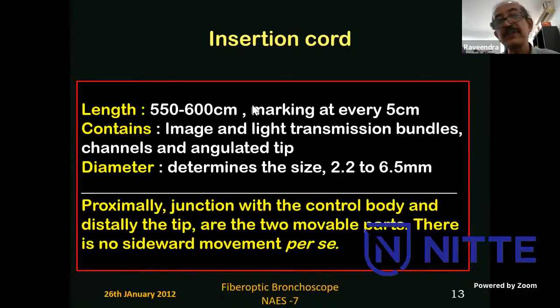When you say the insertion cord, it's a thin, narrow cord, which can be very delicate if it is a fiber optic and not so delicate if it is a non-fiber optic. Length of about 55 to 60 centimeters, marking at every 5 centimeters, except in the distal 10 centimeter, contains the image and light transmission bundle, channels, and angulated tip. So these are the contents of the insertion cord, the image and light transmission bundles, and the channels, which may vary from 1 to 3 or 0 also. If you go for a very small size endoscope like this, they may not have any suction channel also.